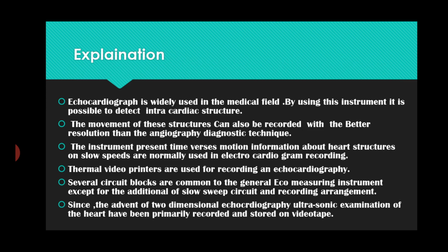Thermal video printers are used for recording an echocardiogram. Several circuit blocks are common to the general echo measuring instrument, except for the addition of a slow sweep circuit and recording arrangement. Since the advent of two-dimensional echocardiography, ultrasonic examination of the heart has been primarily recorded and stored on videotape.